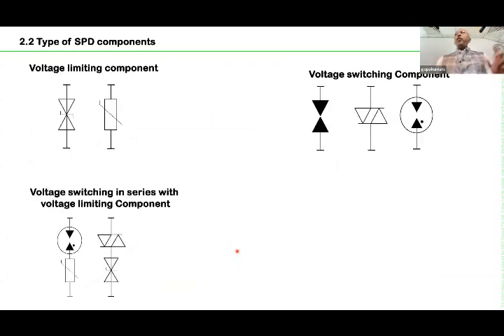Now, the previous ones were the components, the MOV and the GD tube. Once we call this component an SPD, it has to be inside a casing. It has to have its own protective measures. For example, an MOV always fails in short circuit condition, because if it fails in open condition, you cannot detect it. So in order to detect its failure, an MOV always ends its life in short circuit condition.